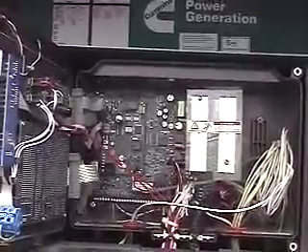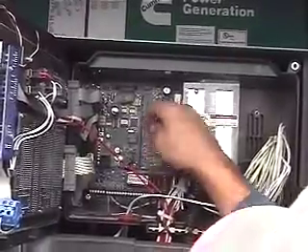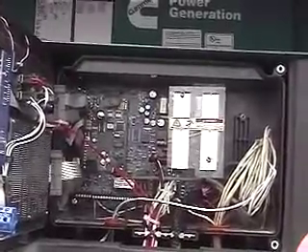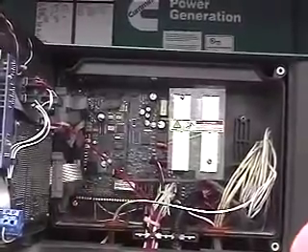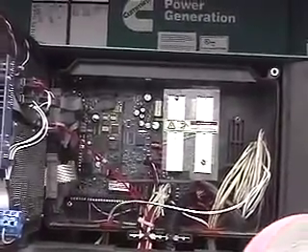So we re-pull that wire. That wire you're looking at right there is Johnson Controls. These ones here? Yeah, no. That's not Cat 4. That should be Cat 4 for that annunciator to work. That is Johnson Controls. Johnson's run these? Yeah. Well, that's not going to let the annunciator work. No, it isn't. I'll have to get a hold of Johnson Controls and find out what. Yeah, I don't know what they're doing there because that's supposed to go to the annunciator, not to Johnson Controls. Yeah, good old Johnson Controls boys.